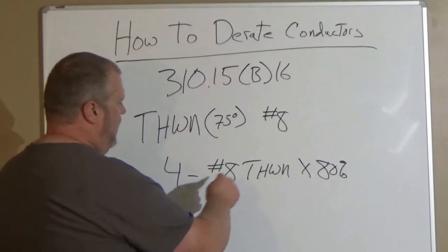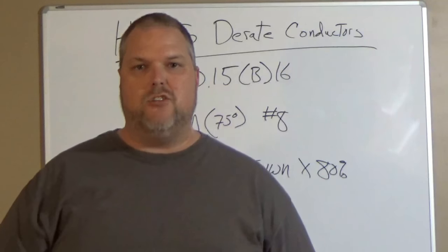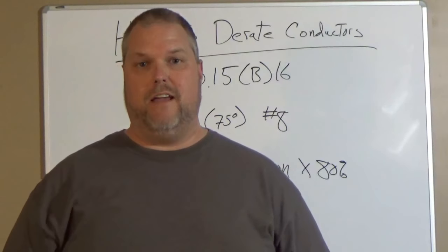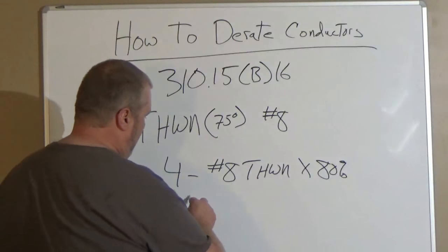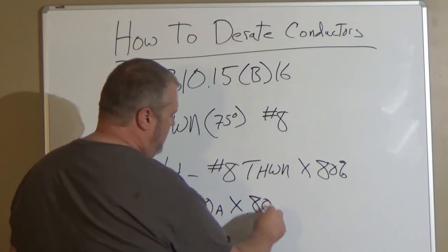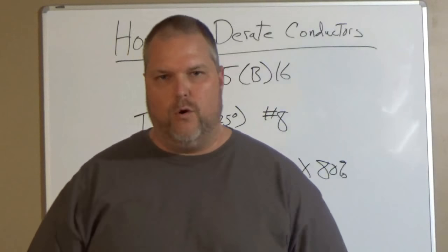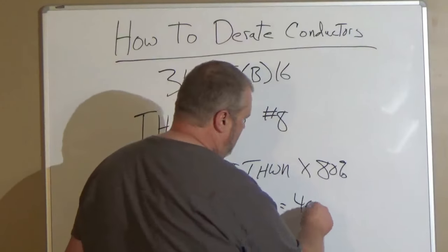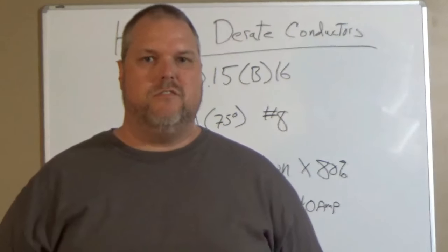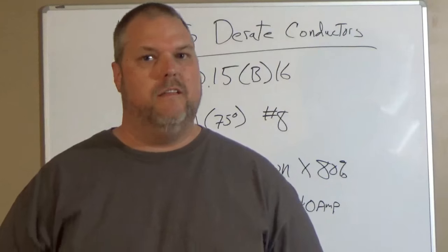So what do I do? If I look into 310.15.B.16, THWN in the 75-degree column, if I go down to a number 8 conductor, it's going to tell me that I can use 50 amps. So I have 50 amps. I'm going to multiply it by 0.80, and that will give me 40 amps. That means that those four conductors running in that conduit is now only rated for 40 amps, not 50 anymore.